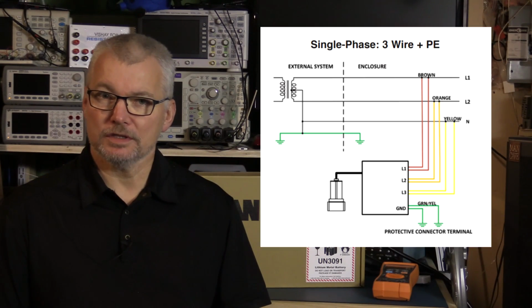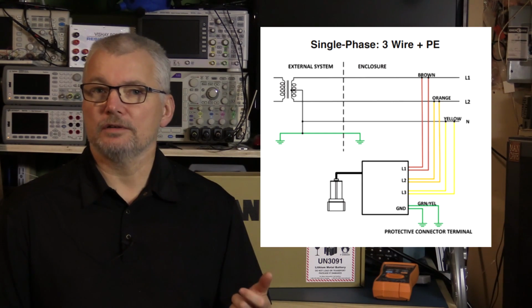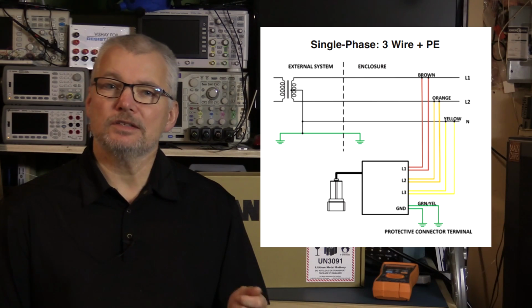And it does this using a whole bunch of redundancy techniques in its design to make sure it's giving you the correct information. That includes having multiple connections to the phases, an internal check before it does the wiring check, etc. And it will also work on AC or DC.